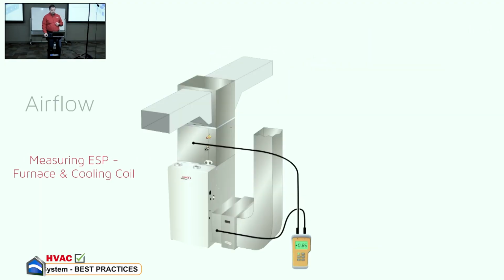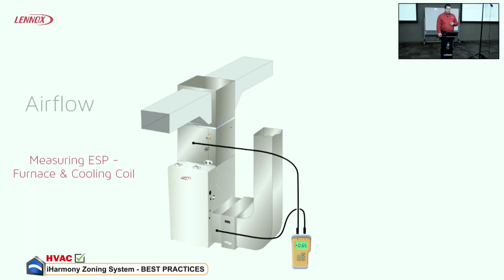As far as airflow, checking static pressure is essential. That's going to get us out of a whole lot of trouble. So, of course, on a furnace system, if we can check it between the furnace and coil, that's ideal. As far as your supply static is concerned, we can check it after that point and do math there on it. Yes, sir. I have a question.